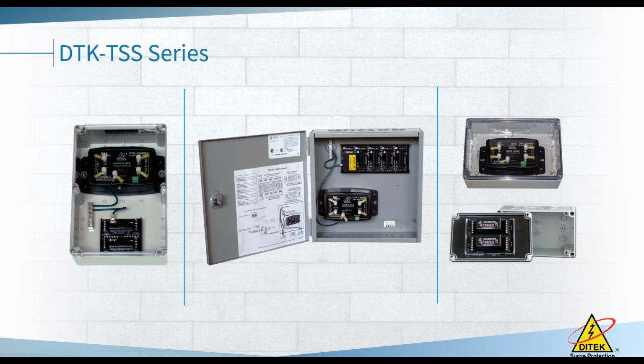The one in the middle is just a TSS1, a bigger device with up to 10 pairs of low voltage protection in that can. On the right you'll see screws where you can mount more bases or even an antenna protector. I've also seen monitoring modules in there if properly spaced. That's our TSS1, and it comes with a test module inside that acts as a pass-through to let you know if a module has failed.